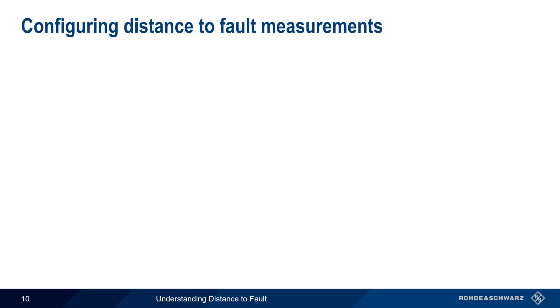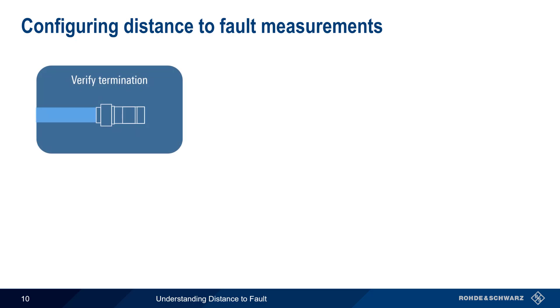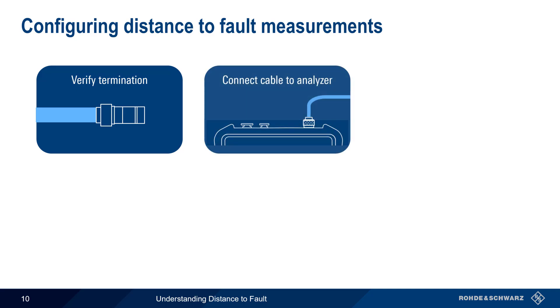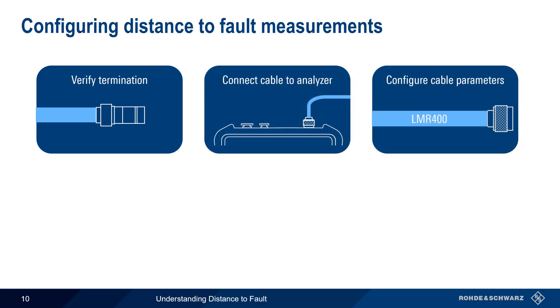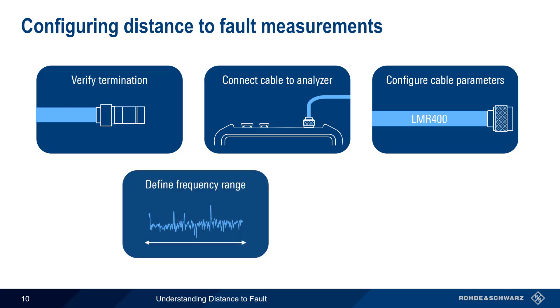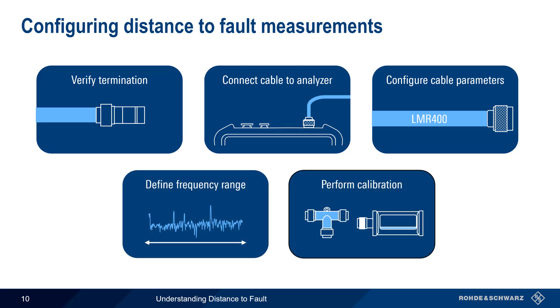There are five basic steps in configuring distance to fault measurements on a VNA. These are: verifying cable terminations, connecting the cable to the analyzer, configuring the cable parameters, defining the sweep frequency range, and performing a calibration. Let's go through each of these configuration steps, starting with the cable termination.